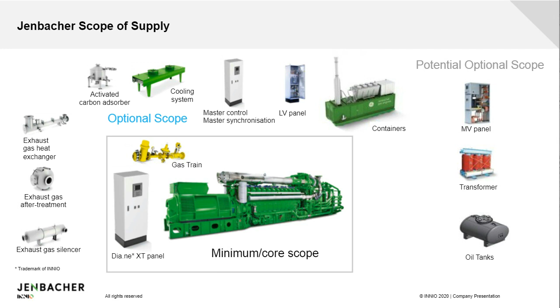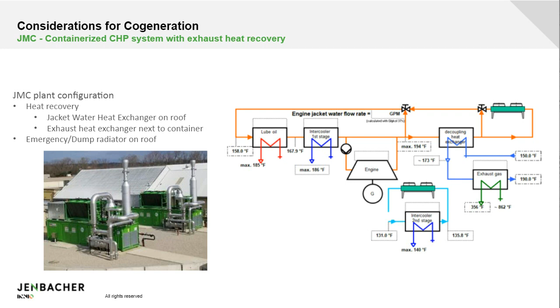As an example, this is a biogas plant with containerized 420 engines — in this case, six 420 engines — a large biogas plant in Europe. We have a configuration I already explained: water is preheated in a decoupling heat exchanger, then sent to the exhaust gas heat exchanger, producing water at a temperature of 190 degrees Fahrenheit. This is the inner system for cooling the engine. Here you can see the application for a sewage plant — this case is in Michigan.